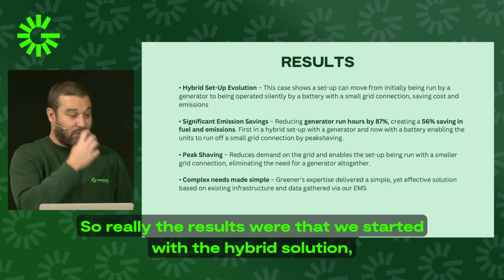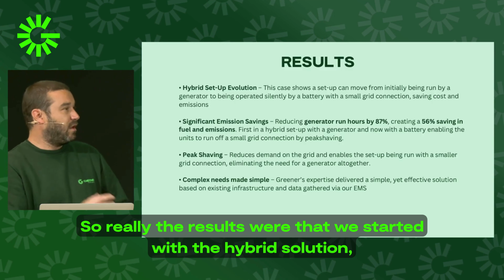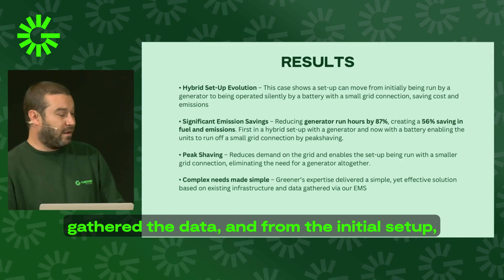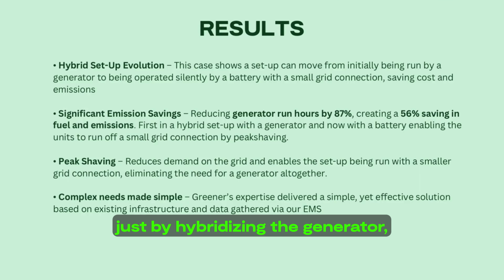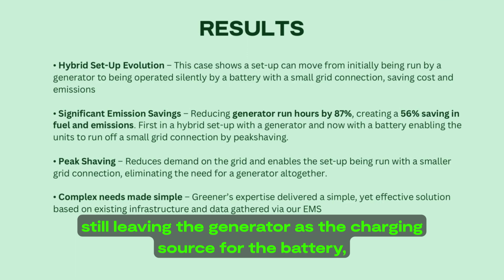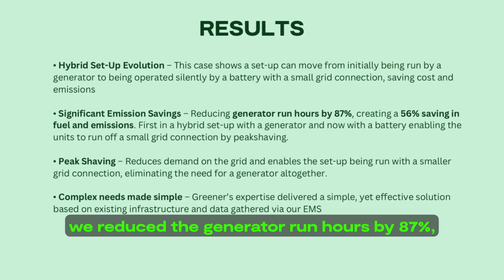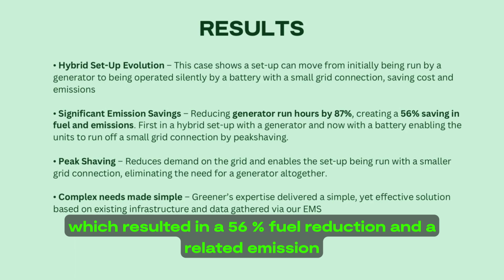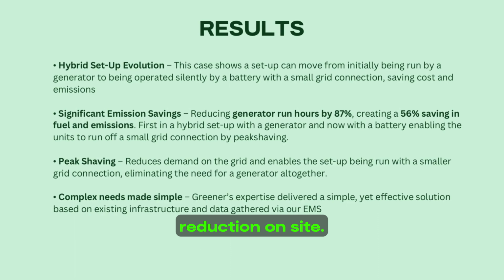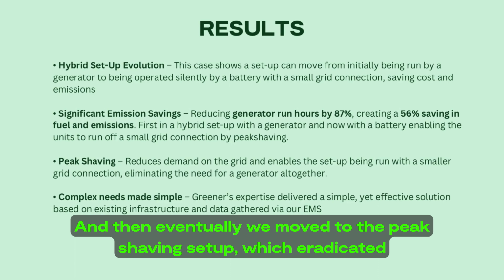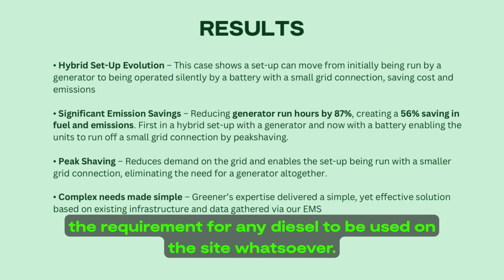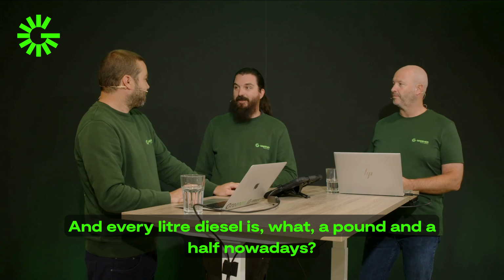So really the results were that we started with the hybrid solution, gathered the data, and from the initial setup, just by hybridizing the generator, still leaving the generator as the charging source for the battery, we reduced the generator run hours by 87%, which resulted in a 56% fuel reduction and obviously related emission reduction on site. And then eventually we moved to the peak shaving setup, which eradicated the requirement for any diesel to be used on the site whatsoever. And every litre of diesel is what?